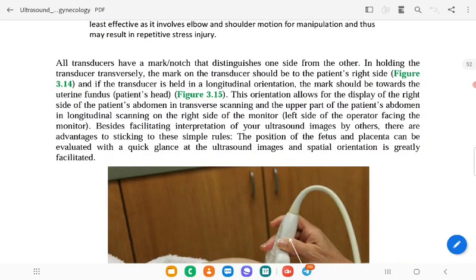All transducers have a mark or notch that distinguishes one side from the other. In holding the transducer transversely, the mark on the transducer should be to the patient's right side, and if the transducer is held in a longitudinal orientation, the mark should be towards the uterine fundus, that is, the patient's head. This orientation allows for the display of the right side of the patient's abdomen in transverse scanning and the upper part of the patient's abdomen in longitudinal scanning on the right side of the monitor.